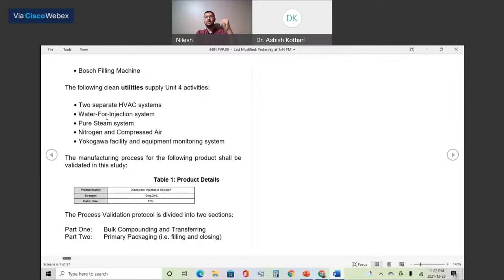Why? Because you have one GMP room, and another room next to your GMP room - so room X has one product and room Z has another product. If we don't monitor or keep controlled differential pressure, then during entry and exit of manpower or material, product powder can escape outside, and cross contamination of the product might occur. That is the main reason we need the HVAC system - it maintains differential pressure between adjacent rooms to prevent cross contamination.